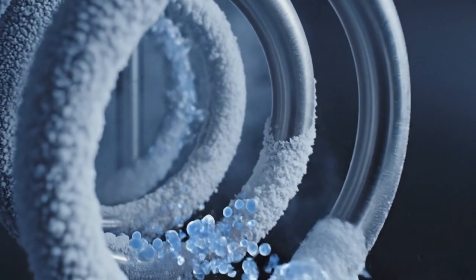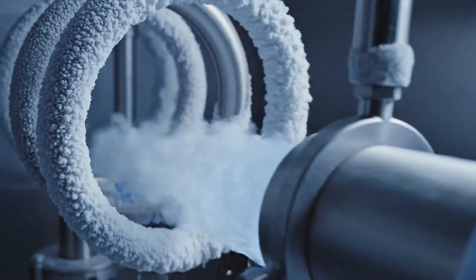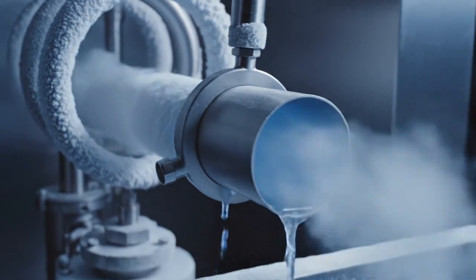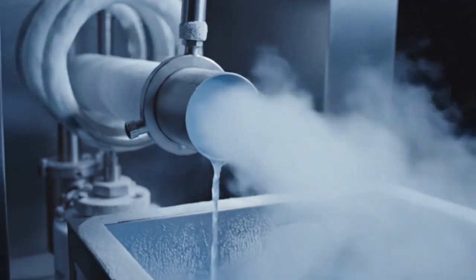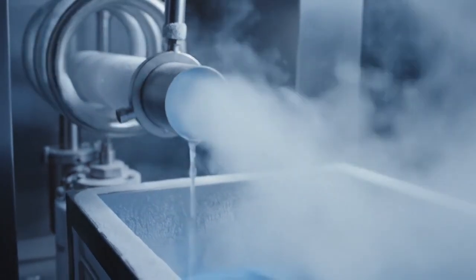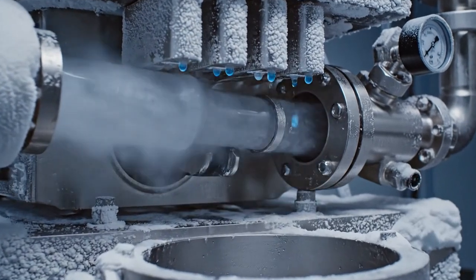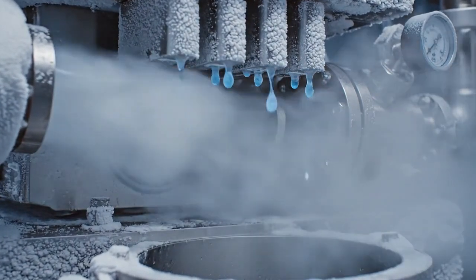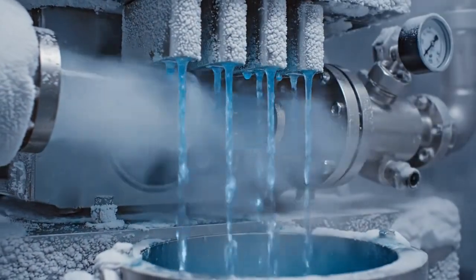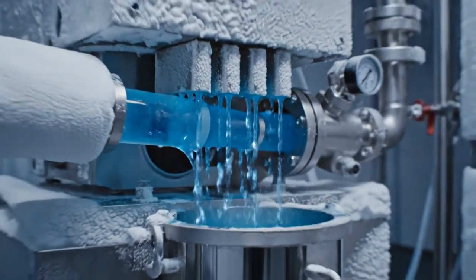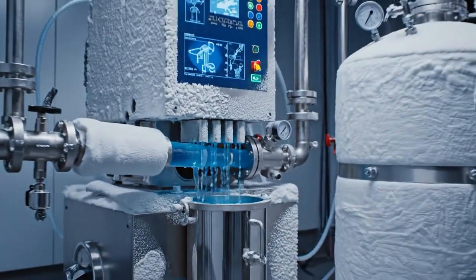The actual gas separation is not assigned to a single component, but is achieved through a multi-stage physical process. This includes gas-liquid separation, the removal of water content, followed by a temperature-based separation step in which oxygen condenses while hydrogen remains in the gaseous phase.